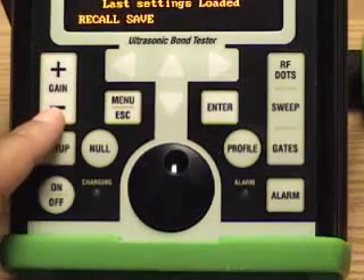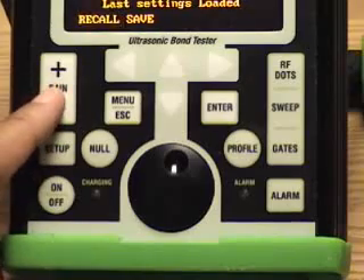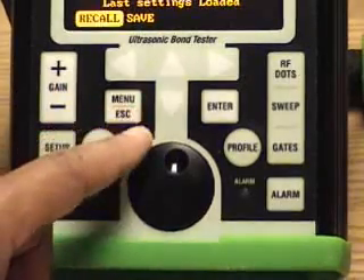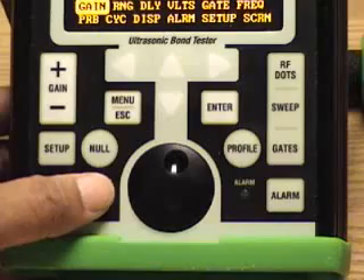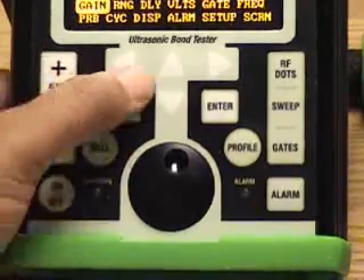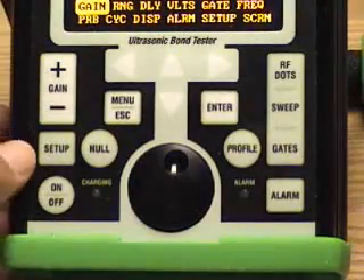Gain controls the overall gain in Resonance Mode, Pitch Catch, and MIA Mode. Menu Escape is a dual function button. Pressing it once will get you into the main menu, and pressing it any time you're making changes in the menu structure will allow you to get out of that change.